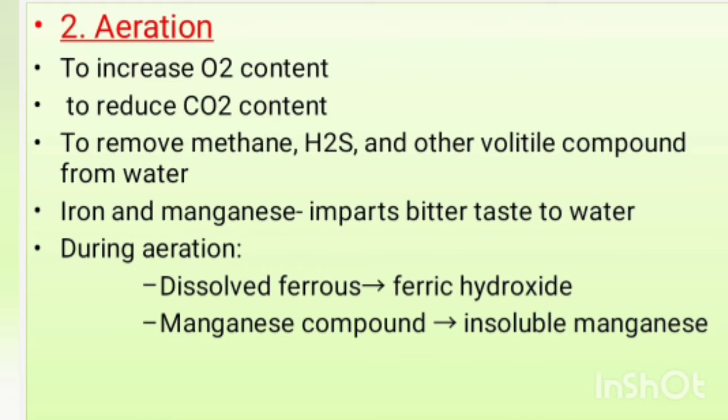That's a problem. So during the aeration process, oxygen is brought into the water, which converts the dissolved ferrous and manganese compounds into insoluble manganese and ferric hydroxide. This insoluble manganese and ferric hydroxide can be removed by sedimentation or filtration procedure.